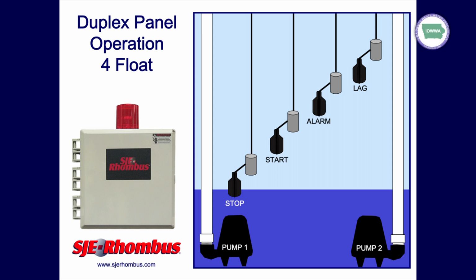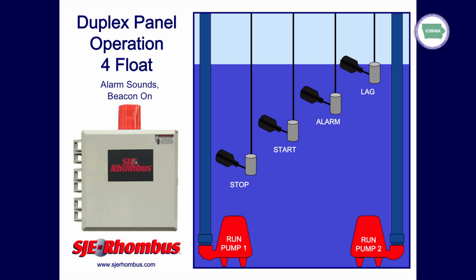Now, the reason I want my lag float at or above my alarm point is if we had a failure of pump number 1. If we had my lag float down here and my alarm float up here, each time we hit the lag position, the pump that's still working is going to kick in and take care of the load.